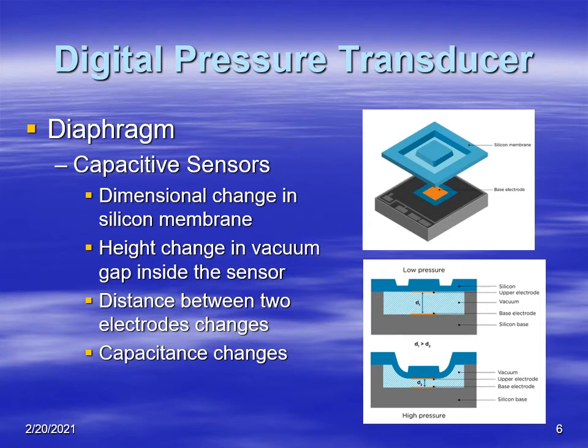Another type of diaphragm is a capacitive sensor. This means you have a silicon membrane layered over an evacuated chamber, a vacuum, inside the sensor. As pressure changes, you get deformations in the membrane. It flexes up and down. If you put two charged plates, one on the base and the other on the bottom of the membrane, then as the distance between the membrane and the base of the sensor increases or decreases, you get changes in capacitance. So the change in capacitance is directly related to the change in pressure.